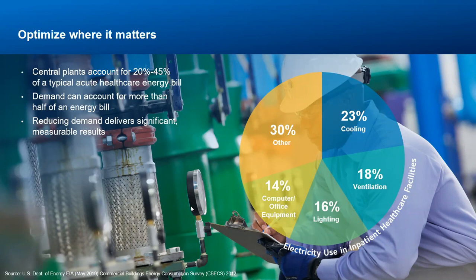And certainly the biggest portion of that HVAC energy is the central plant. Looking at electricity alone, cooling is about 23% of the average inpatient healthcare facility's energy use. So if you like the Pareto principle — the 80-20 rule, focusing first where you get 80% of the impact from 20% of the effort — focusing your smart building efforts on the central utility plant can be a really good place to start.